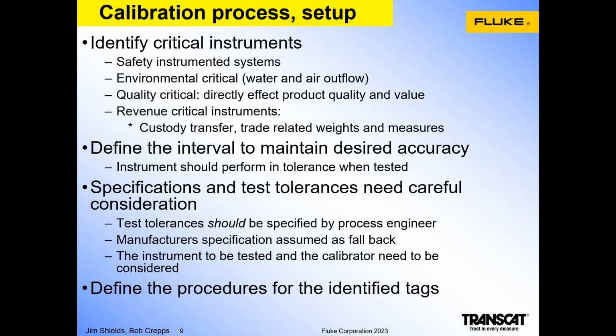So in starting up a process, initially, you would want to identify the instruments that are critical. Firstly, of course, in the lineup of critical instruments, you might want to include the safety instrumented system instruments that are responsible for making the measurements in the safe operation of the plant, startup and shutdown. The environmentally critical instruments that impact water or air flowing into the environment and are regulated by the EPA. Quality critical devices that affect product quality and the value of the product being manufactured in the facility, and revenue critical instruments, as I mentioned before, especially custody transfer and other trade related weights and measures.